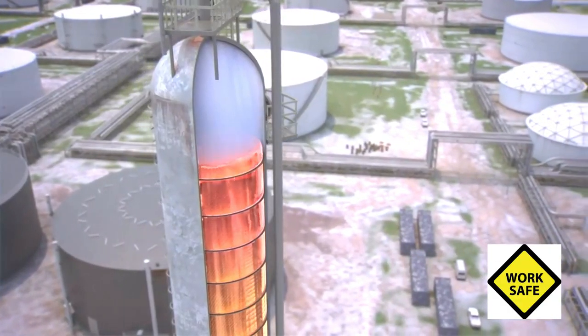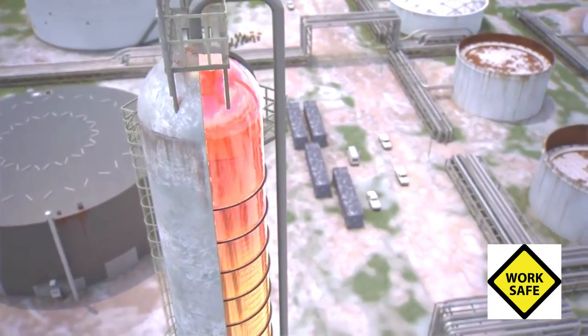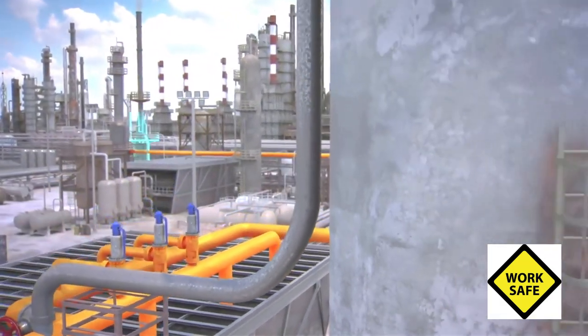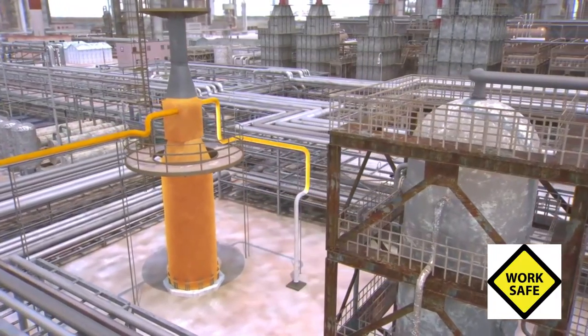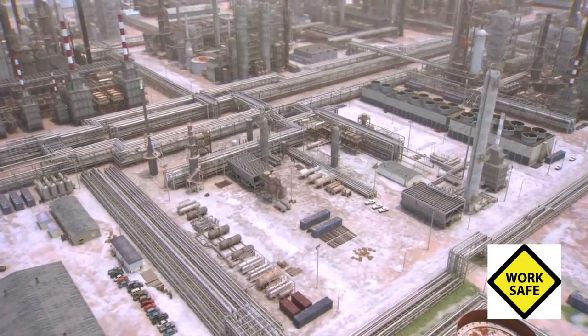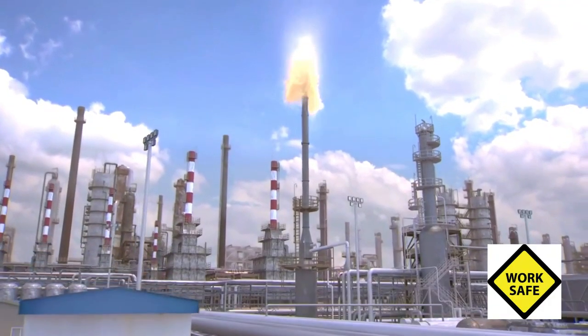Over the next few minutes, the hot feed entering the tower caused the liquid inside to start to boil and swell. Liquid filled the tower completely and began spilling into the overhead vapor line, exerting great pressure on the emergency relief valves 150 feet below. At 1:14 p.m., the three emergency valves opened, sending nearly 52,000 gallons of flammable liquid to the blow-down drum at the other end of the ISOM unit. Liquid rose inside the blow-down drum and overflowed into a process sewer, setting off alarms in the control room. But the high-level alarm on the blow-down drum failed to go off. None of the operators knew of the catastrophe unfolding in the ISOM unit.